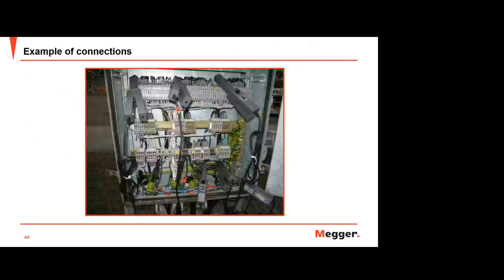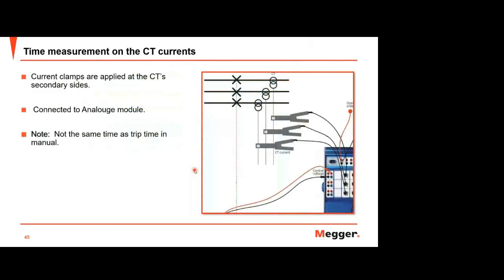This is the example of real connection. This is to measure load current CT on the RST, and this is to measure the coil for both closing and tripping. For this case, we did it offline, just for testing, not the real one for trip, meaning we do it on the system without the load actually. Yeah, this is the connection of the current.